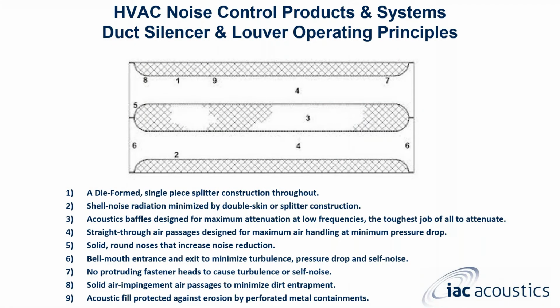Our duct silencer design. I like to go over this because the simple effect is that you see on the left, and then look on the right, they are the same. This is our solid round noses that help increase noise reduction. At the same time, it has a bell mouth entrance and exit, which minimizes turbulence, pressure drop, and self-noise. Case in point, our silencers are rated for forward and reverse flow on either end, so it doesn't really matter which way you install this.